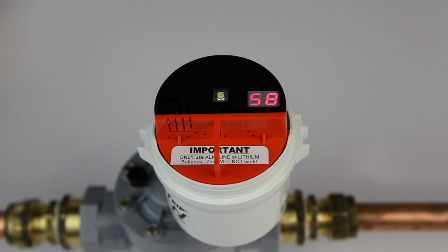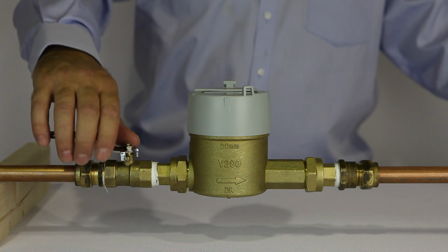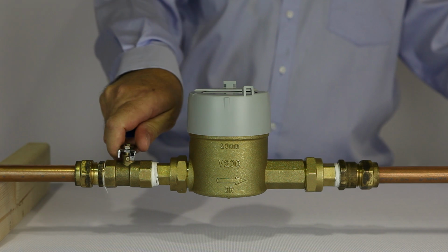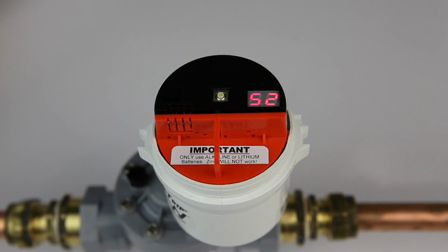But this time, turn off the main incoming tap to the property during the 60-second countdown, and the countdown should stop immediately as you're cutting off the main supply. If the countdown continues on down to 0, even after the main supply is cut, it means the flow sensor must be jammed or damaged or the control unit needs servicing.